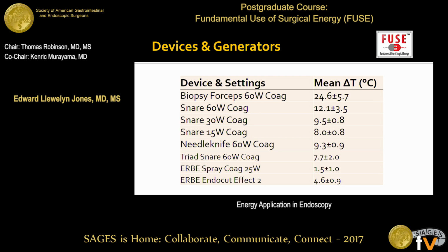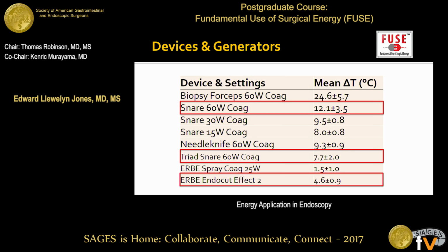Just to compare apples to apples, we looked at your standard snares at similar settings using older and newer generators. The big significant thing I want to emphasize here is that as technology improves and we've gotten generators that modulate the output and reduce it as your tissue impedance changes, we can see that we have less accidental stray energy transfer.